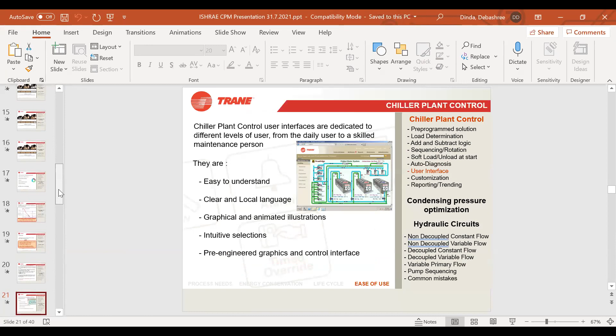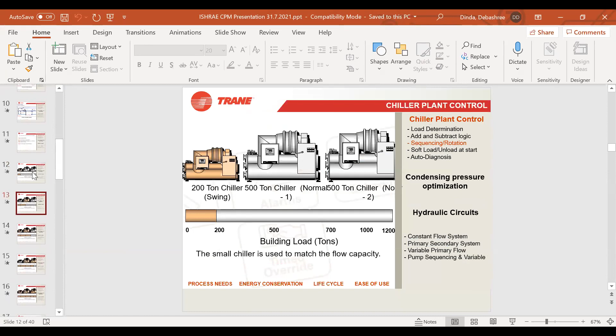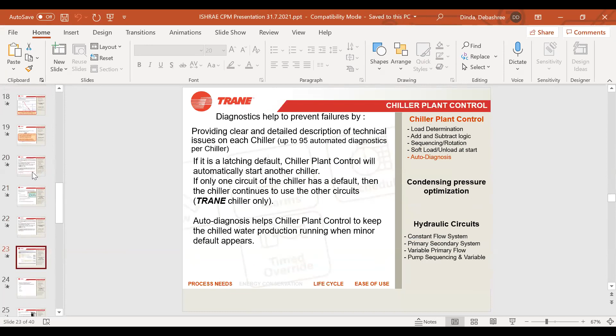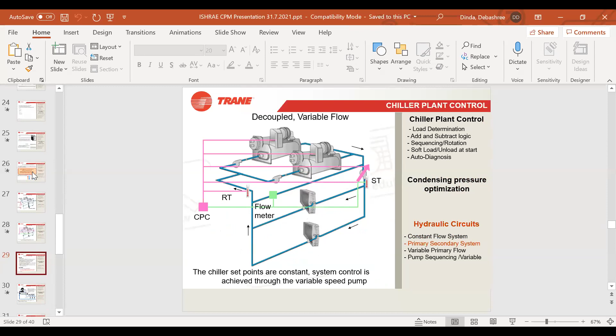Sorry to interrupt. Considering your sequencer and the CPM, the major difference is your chiller plant manager comes with artificial intelligence built in, so it will run the complete plant in such a synchronized manner that you achieve maximum energy efficiency. The goal of the chiller plant manager is achieving maximum efficiency, kW per TR, for the complete plant, not only chillers. Your chillers, pumps, cooling towers, everything put together, it will try to run all the equipment in such a sequence or combination that the output of the complete plant is the best. So that is the difference between your sequencer and your chiller plant manager.